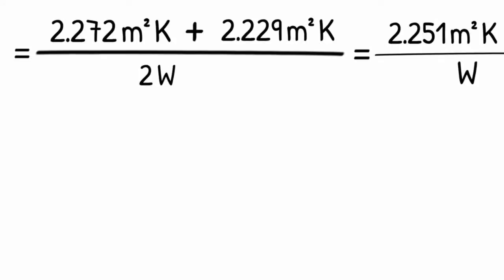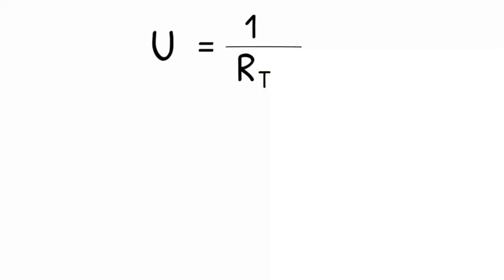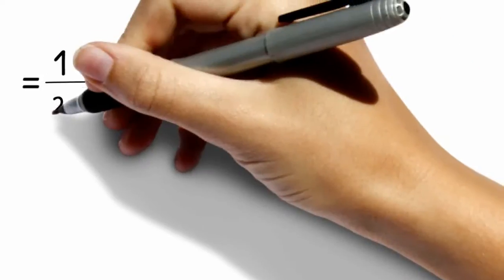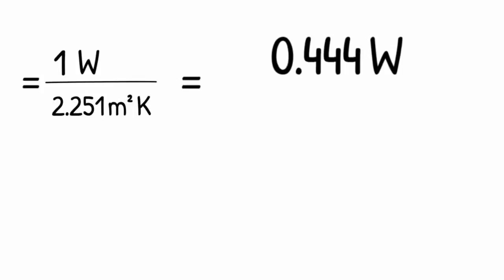The U-value is still the inverse of the total resistance and in our case the inverse of 2.251 square meter times kelvin and the watt then goes on top of the bar. This gives us 0.444 watt per square meter and kelvin which is our result.